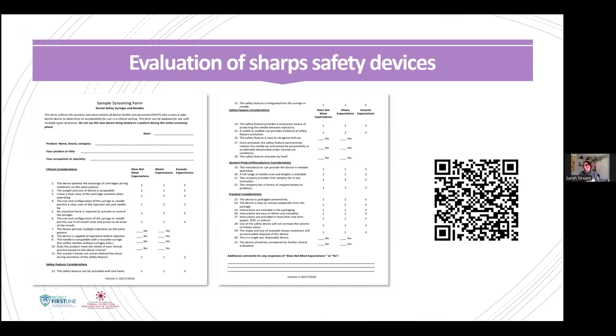The CDC has some dental-specific sharp safety device evaluation forms available. And really, your sharp safety devices should be evaluated on an annual basis. And these forms give you a really nice objective way to evaluate those. And when you evaluate sharp safety devices, everybody that uses that device should be included in the evaluation. And you should really talk about it as a team.